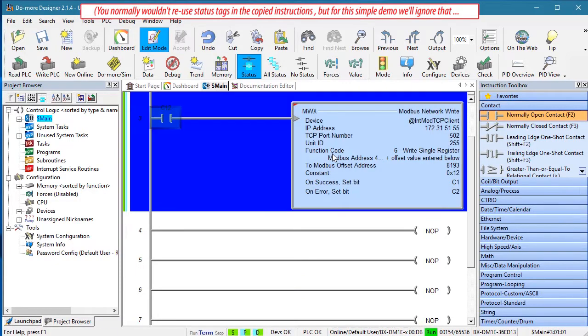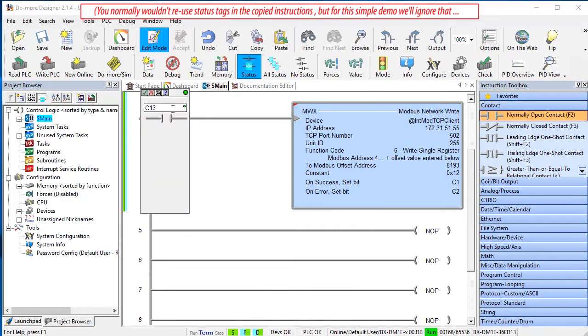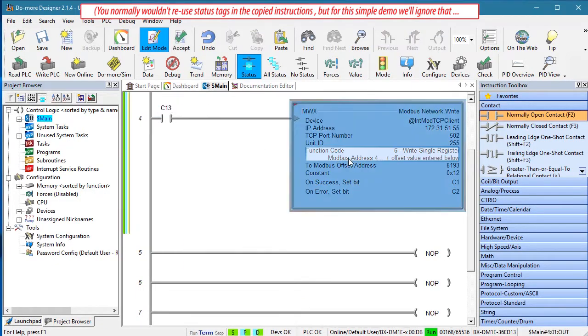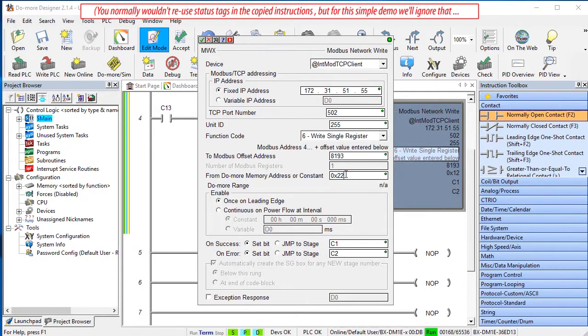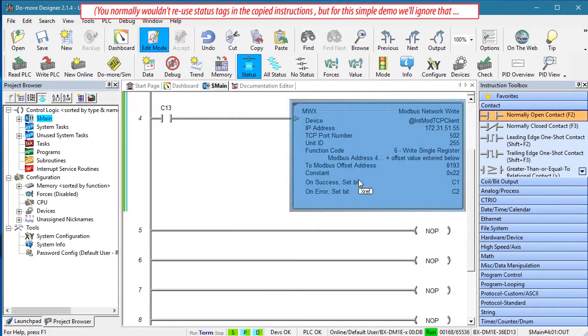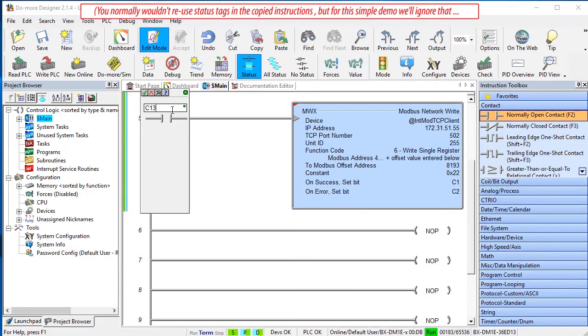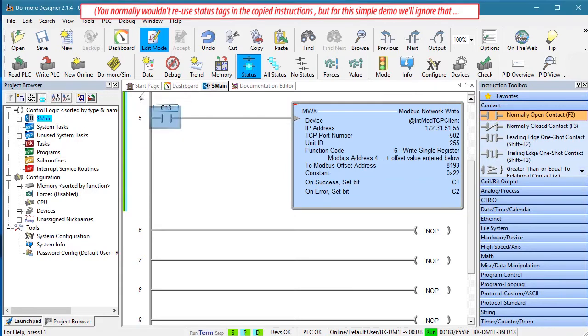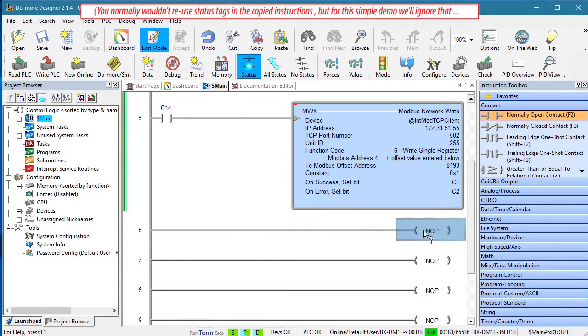Copy and paste that again and let's have C13 write to that same Modbus address but set the bits to run in reverse. Copy and paste again and have C14 write to that same Modbus control address but set the bits to stop the drive. And let's add an end.